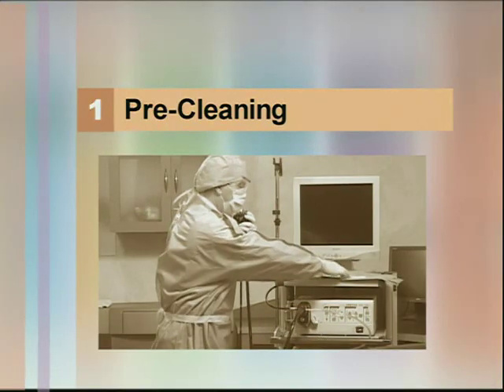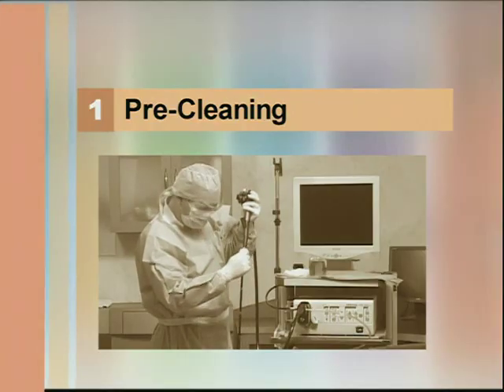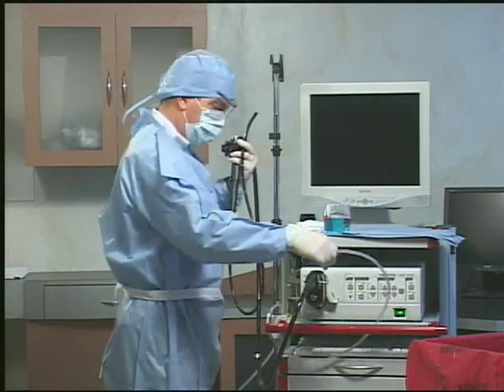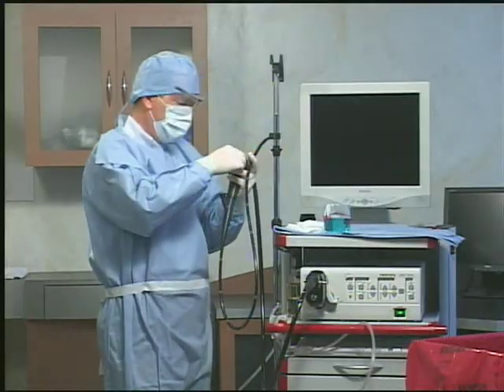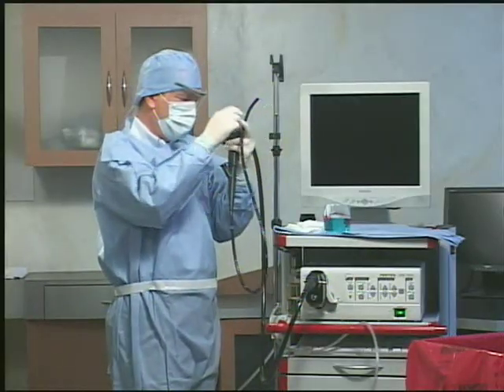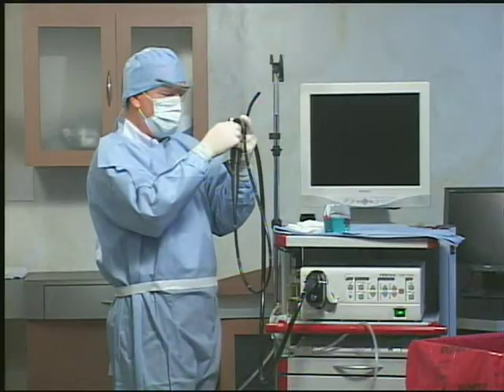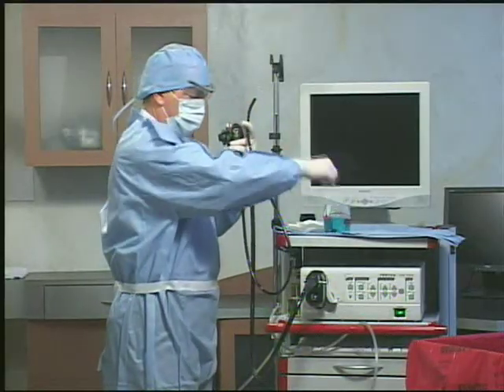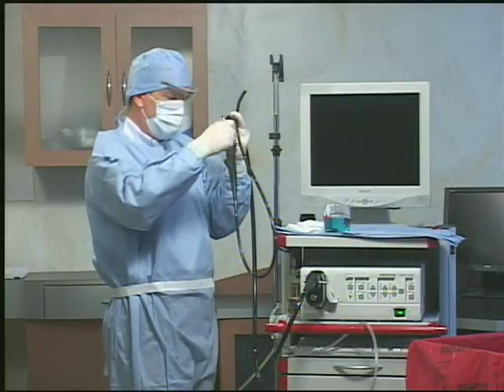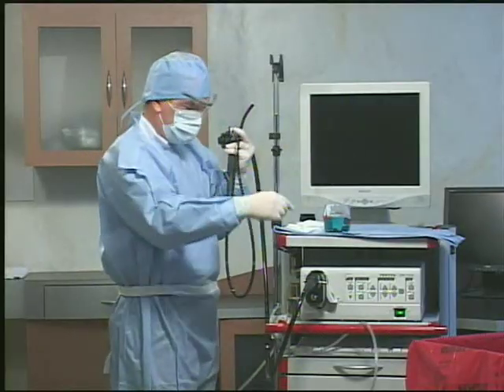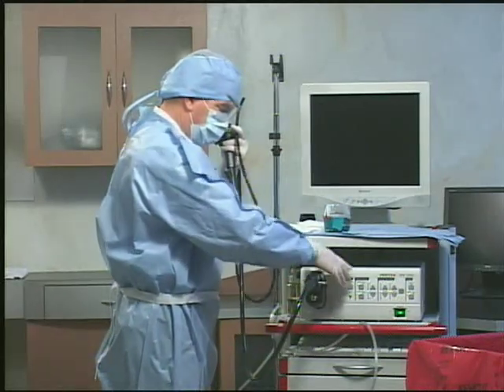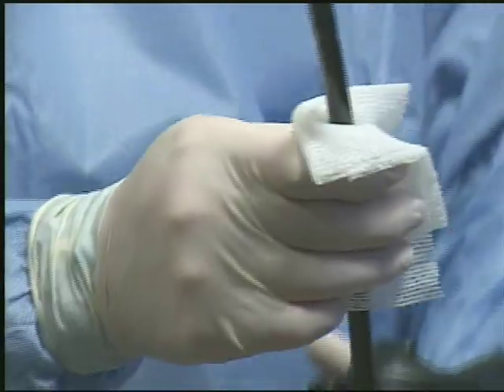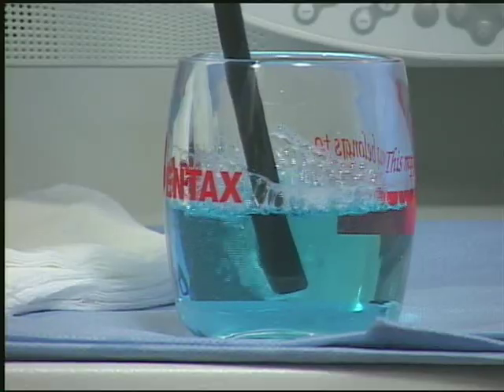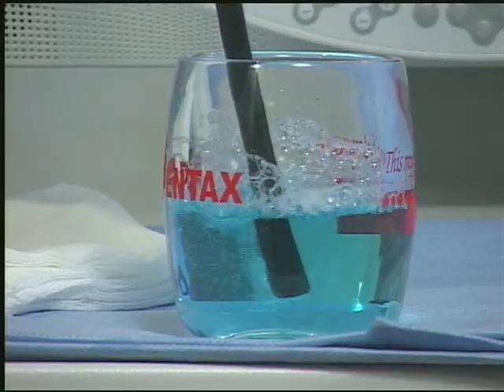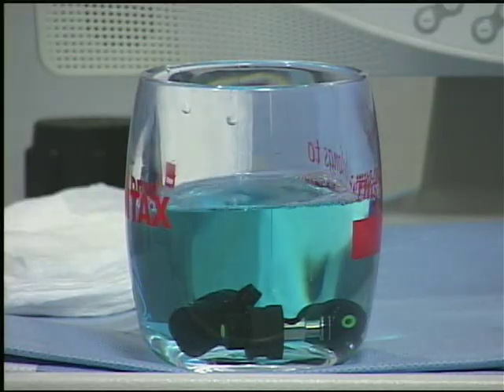Pre-cleaning should be performed in the examination room immediately after the endoscopic procedure. If the endoscope or scope components are left unclean for some time after use, dried blood, mucus, contrast material, or other patient debris may cause damage to the instrument or component, or may interfere with the ability of the reused item to be adequately reprocessed as intended. Pre-cleaning goals: to remove gross patient material from the external surfaces of the endoscope, to purge internal channels and prevent drying of debris within the channels, and to begin pre-soaking of the removable scope components.